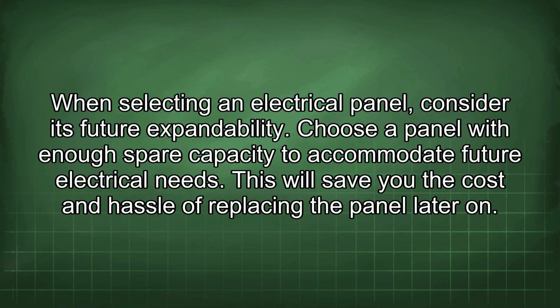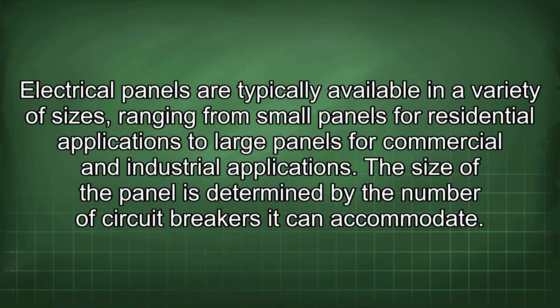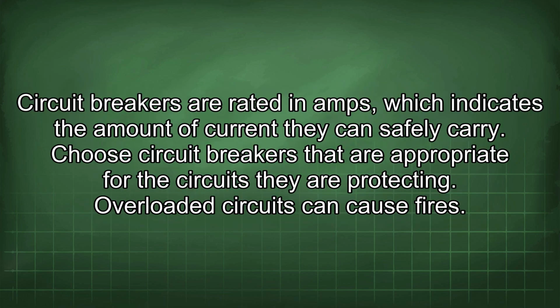When selecting an electrical panel, consider its future expandability. Choose a panel with enough spare capacity to accommodate future electrical needs. This will save you the cost and hassle of replacing the panel later on. Electrical panels are typically available in a variety of sizes, ranging from small panels for residential applications to large panels for commercial and industrial applications. The size of the panel is determined by the number of circuit breakers it can accommodate. Circuit breakers are rated in amps, which indicates the amount of current they can safely carry. Choose circuit breakers that are appropriate for the circuits they are protecting. Overloaded circuits can cause fires.